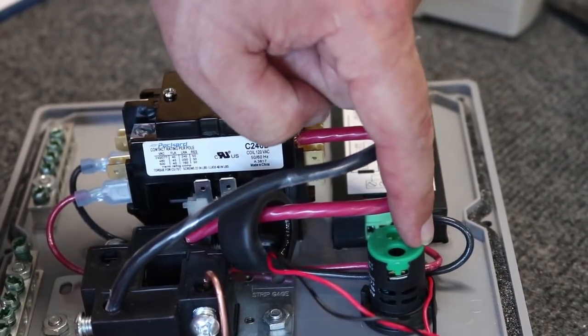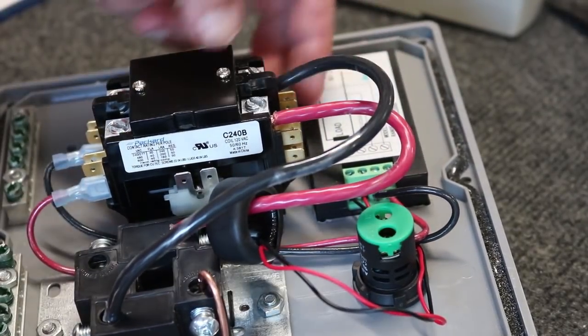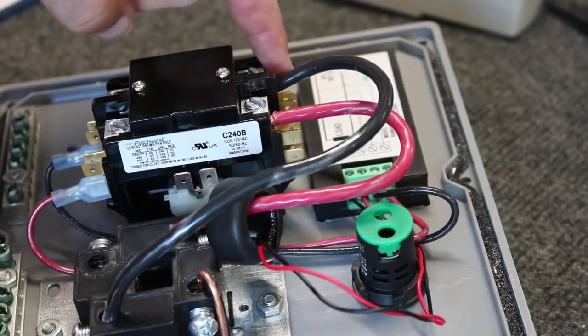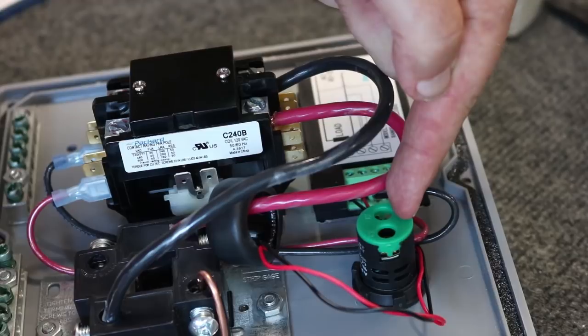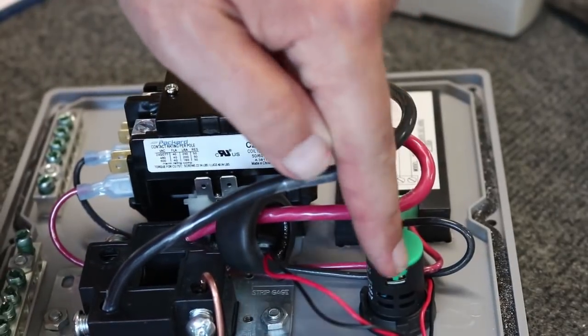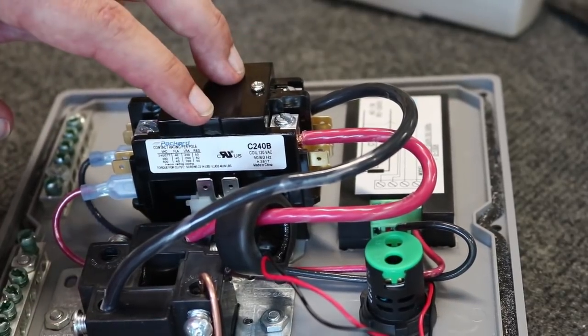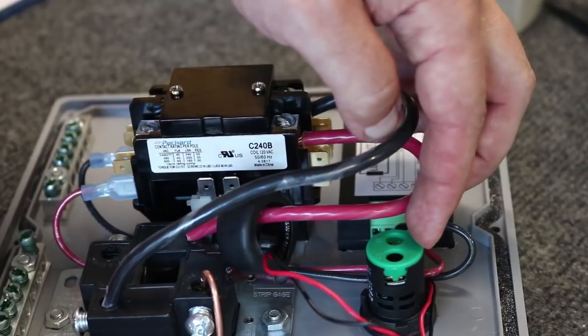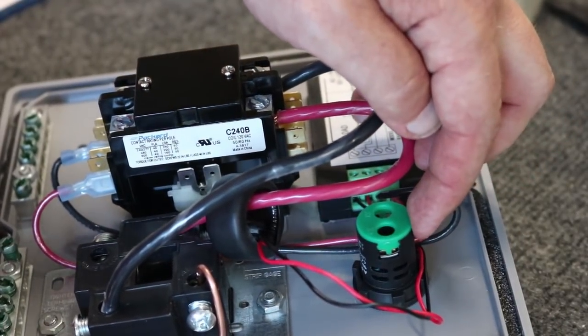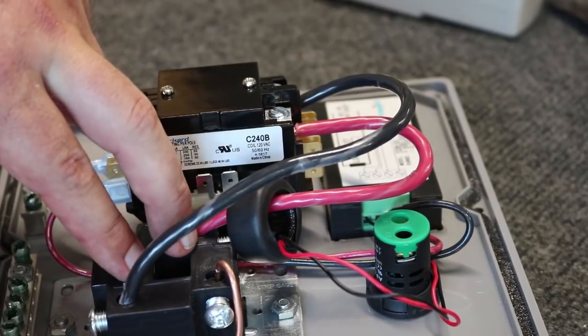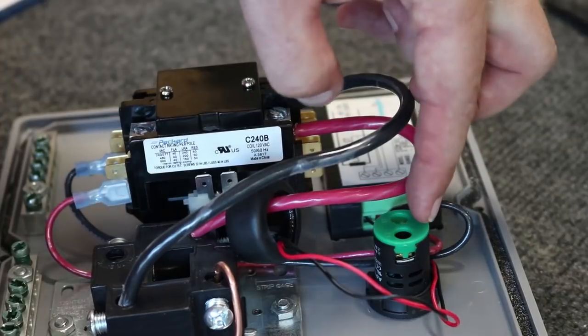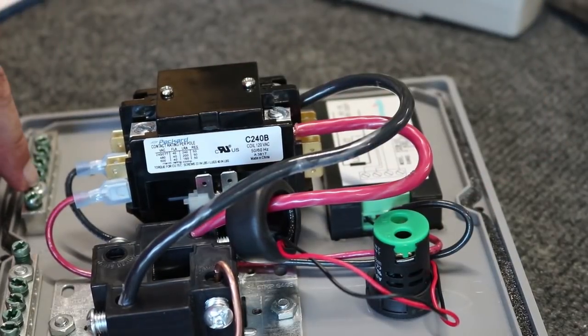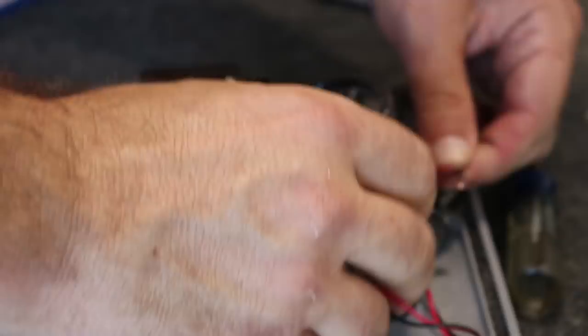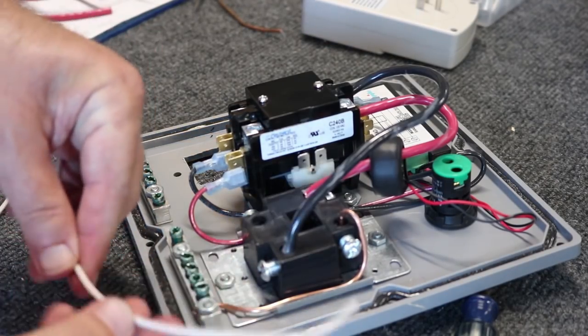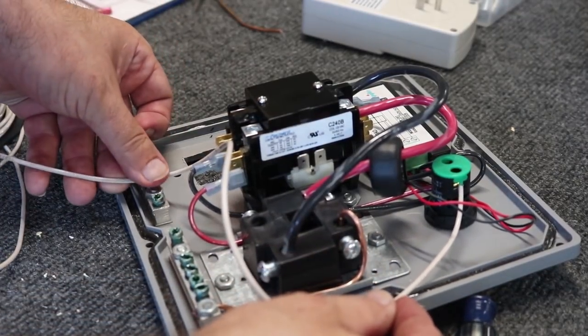Now up at this power indicator light, that's 120 volts. So what we'll do is we'll tap off this switched black hot wire to send power to it, and then to complete the circuit we'll use a neutral wire coming back to the neutral bus. So keep in mind the contactor is switched, so we'll have switched power, but it's going to be 120 volt power to the indicator light, which will show us whether or not there's power to the 240 volt electric outlet. So one short black wire from the switched hot to the bulb, and then a white wire back to the neutral bus. And then to complete the circuit, we'll use the neutral from the light back down to the neutral bus.